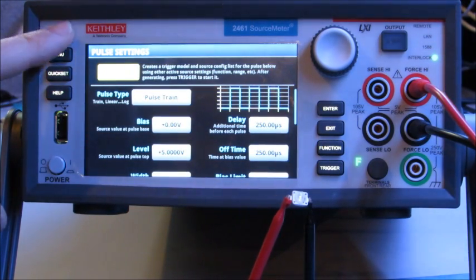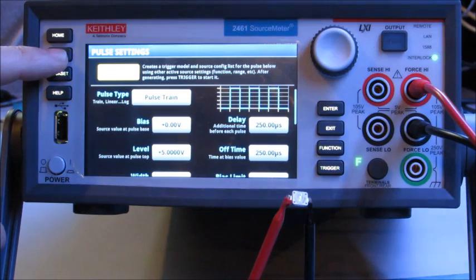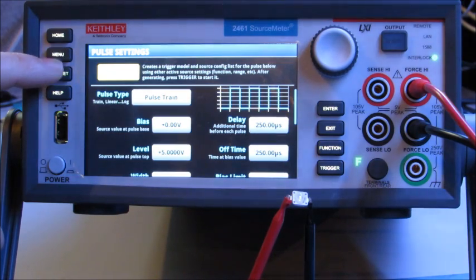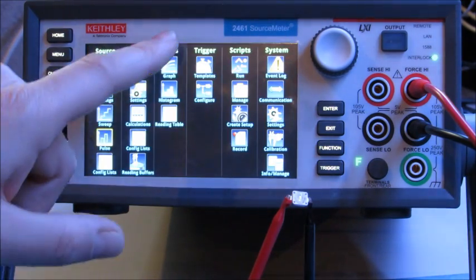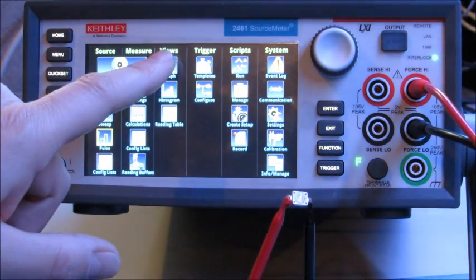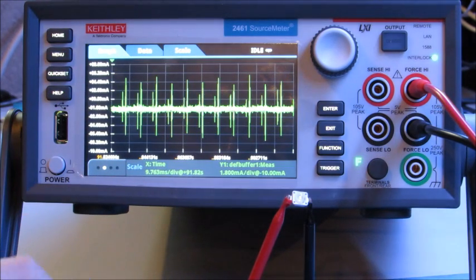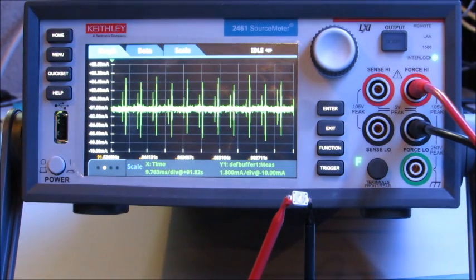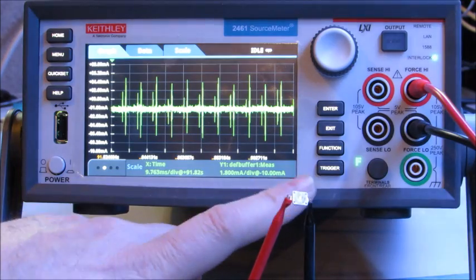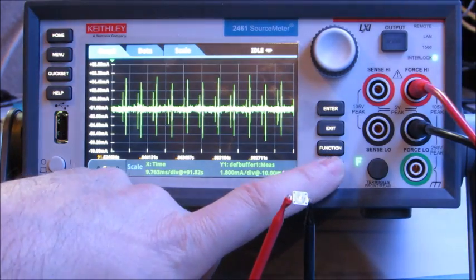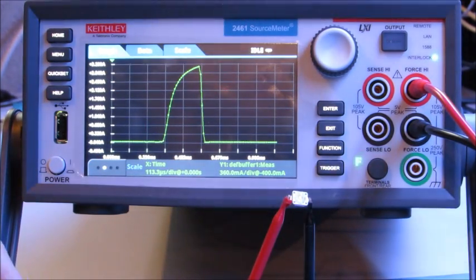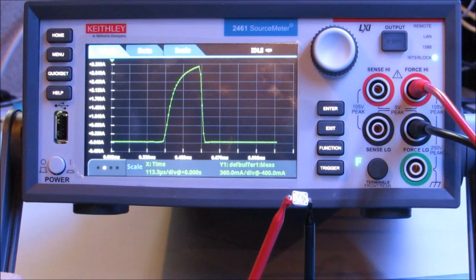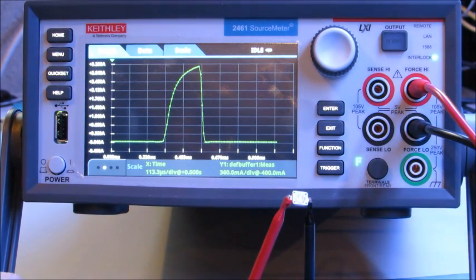So that I can view the graphing capability of the digitizer, I'm going to hit menu. I'm going to go to views and view graph. I haven't hit the trigger button to start the test, but let's do that right now. So when I hit trigger, you saw the LED flash and there is the measured current pulse at 100,000 readings per second.